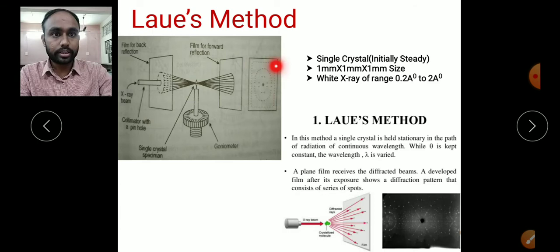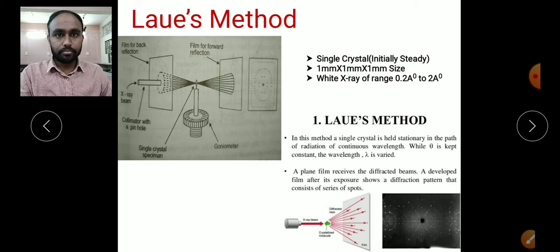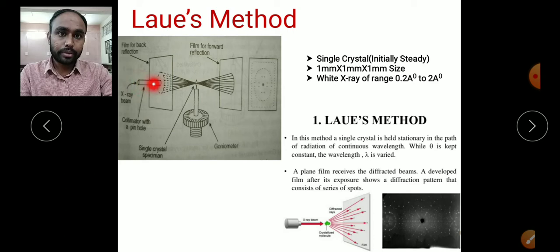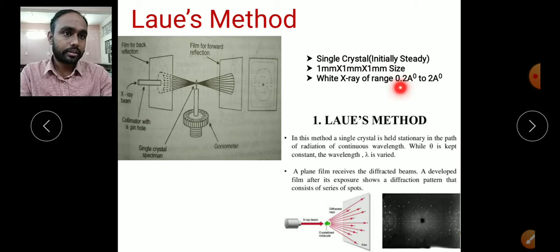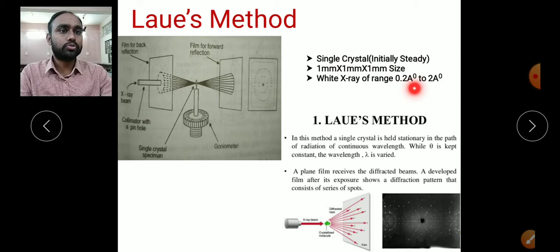The collimator makes the X-ray beam parallel — whatever the X-ray beam taken from the source, making it parallel is done by the collimator. The X-ray used here is white X-ray, not monochromatic. White X-ray contains all wavelengths; it has a range from 0.2 angstrom units to 2 angstrom units.